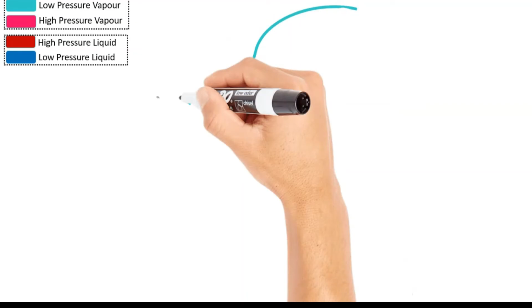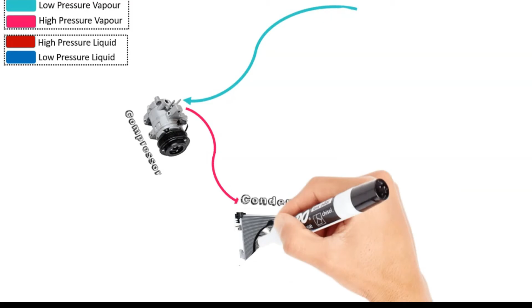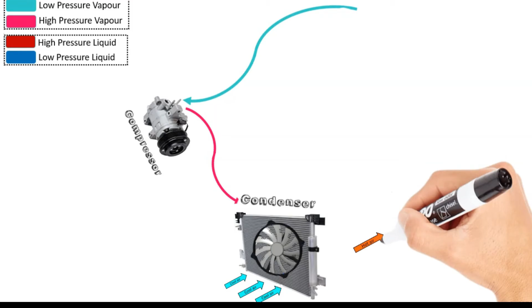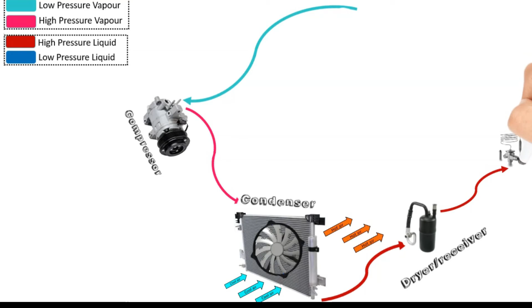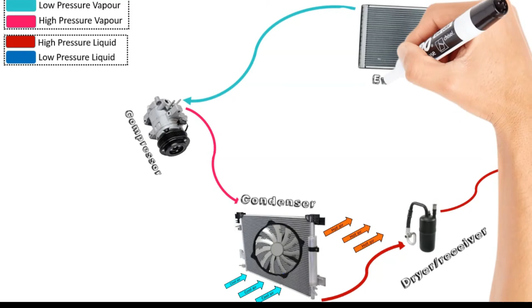Low pressure refrigerant vapor enters the compressor. Inside the compressor, the process of vapor compression takes place. Low pressure refrigerant vapor now leaves compressor as high pressure and temperature vapors. This high pressure and temperature vapor enters the condenser along with the lubricant oil. During circulation of this high pressure and temperature vapor in condenser, heat is released to ambient air. As a result of phase change process, the refrigerant vapors are now converted into liquid. Now this high pressure and temperature liquid enters into receiver dryer, where filtration of debris and vapor takes place from liquid refrigerant. Filtered high pressure and temperature liquid enters expansion valve and leaves as low pressure liquid and vapor mixture. The evaporator receives low pressure liquid and vapor mixture, which absorbs the heat from the cabin air and becomes completely superheated vapor at the exit.